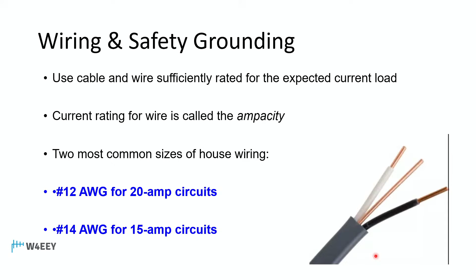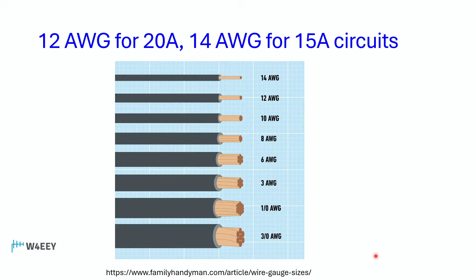This used to be more of an issue back in the incandescent lamp time, when we were actually using more power for lighting and things than we are now. But you don't want to put a 20 amp circuit breaker on a number 14 wire, because it doesn't have the ampacity to carry the 20 amps and could actually cause a fire. And so when we're talking about the American wire gauge, here's some comparative sizes where, from the smallest to 3/0 there, the big one.